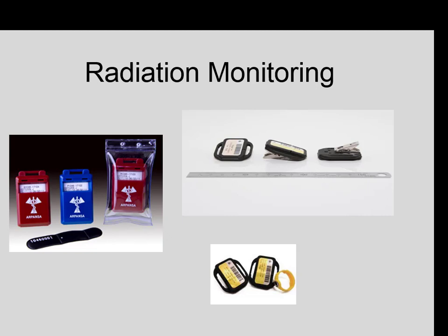In the CCL, in the cardiac cath lab, typically you will wear your badge underneath a lead apron. This is because we're interested in your exposure and we're not interested in the exposure to the lead apron.